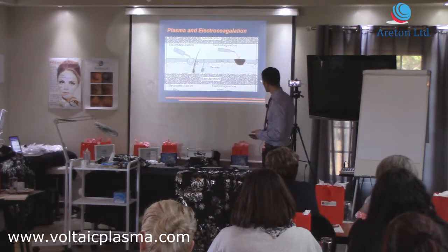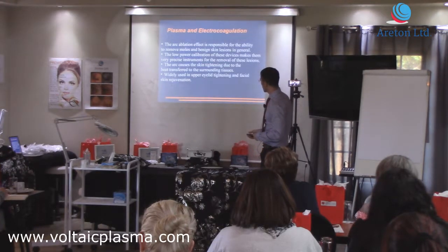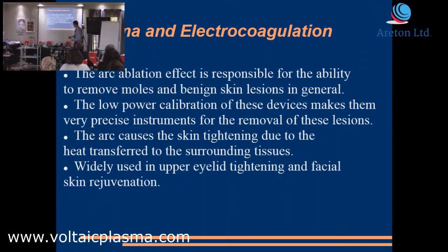The main difference between our units and electrocoagulators is that the power settings of our devices are much, much lower. If you use our devices, normally their low power calibration makes them very precise instruments for removal of lesions and skin tightening. If you use an electrocoagulator for the same purposes, you're going to find it extremely difficult. You may be able to do it safely, but normally their power settings are too high because they're meant to destroy tissue and coagulate well, so their power level is very, very high.